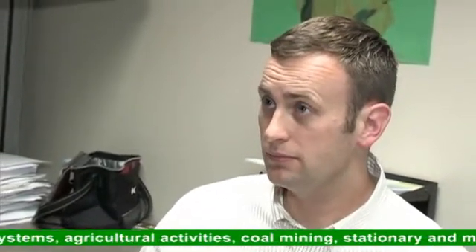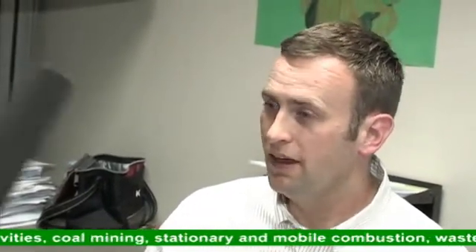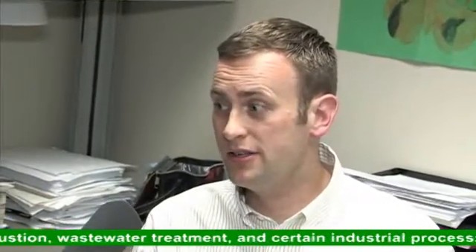Can you tell me a little bit more about what it takes to put one of these in the field? The one thing that's really nice about the methane analyzer is that it's got very low power consumption, so it'll actually run on solar panels. We don't need AC power or large generators. We can put them in a lot of very remote places with small solar power systems, and because it's open-path, it doesn't require pumps or enclosures of any kind, so it's a lot easier to put in remote places than other instruments.